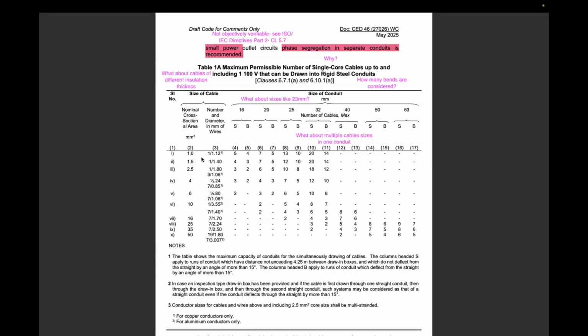However, there are concerns. For example, it says that if you have a 20 millimeter conduit, under certain conditions you are allowed five 1 square mm conductors, and under certain conditions you are allowed four. Similarly, for 2.5 square mm in 25 millimeter, under certain conditions you are allowed 10, and under certain conditions you are allowed 8. S talks about where you have a run not exceeding 4.25 meters between draw-in boxes and do not deflect by more than 15 degrees, and B applies to runs which deflect from the straight angle by more than 15 degrees. But now there is one problem. In one conduit, you will not have only one size of cable. For example, you may run two circuits through a conduit.